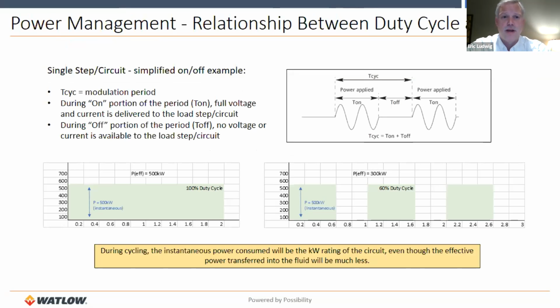So let's talk a little bit about power management now too. Obviously a lot of power is being consumed by these large electrical heaters that need to be switched on and off. What you see in the upper right-hand corner is a depiction of how the electrical signal or the power signal is switched. When it's on, which is represented by the T on in the graph, you're getting full power into the system. And when it's off, it's obviously off and you're getting no power. The T on plus the T off is represented by the T cycle, which is what we call the modulation period. So that's the control period that we work within. And we can manipulate the time that the power is on versus the time that the power is off in there to supply a certain effective power or effective heat into the fluid.